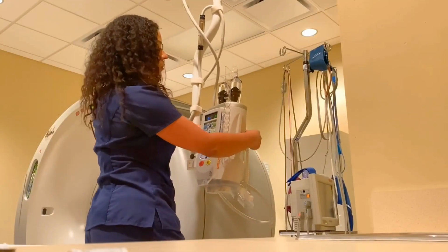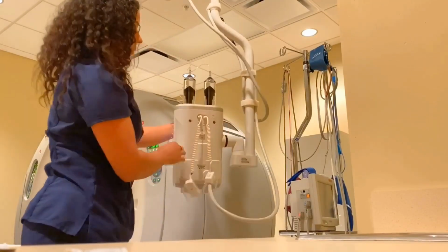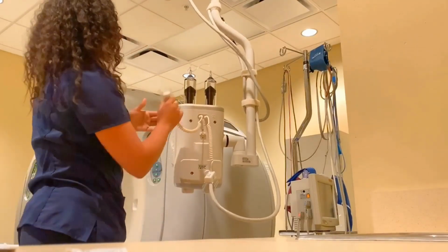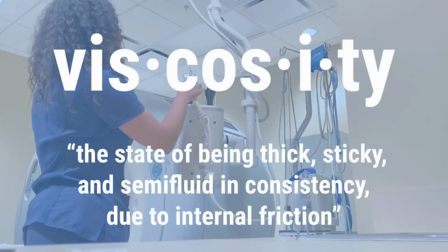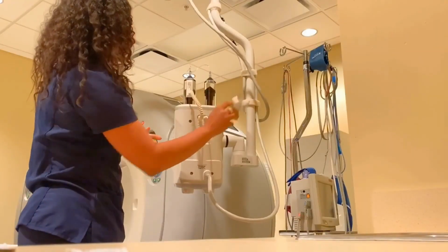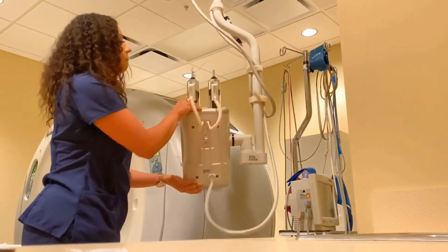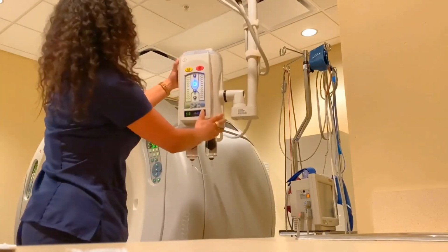So the last step setting up the power injector is to pop on these warmers. And these warmers help with viscosity, which is the thickness of the contrast. The thinner it is, the easier it is to flow, and warming it thins it. So our power injector is prepped, and now we are pretty much ready for the patient.